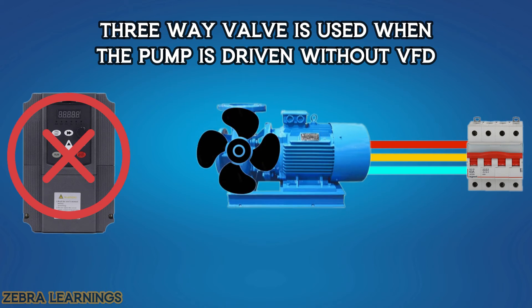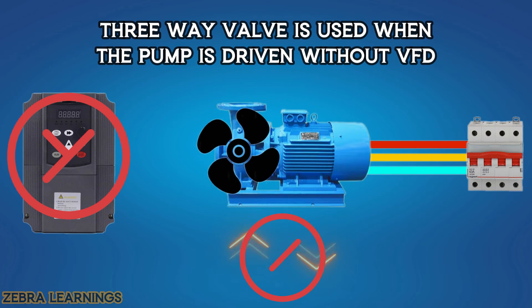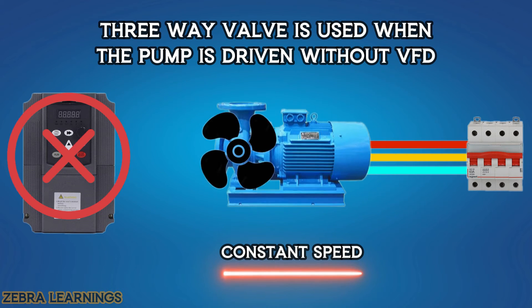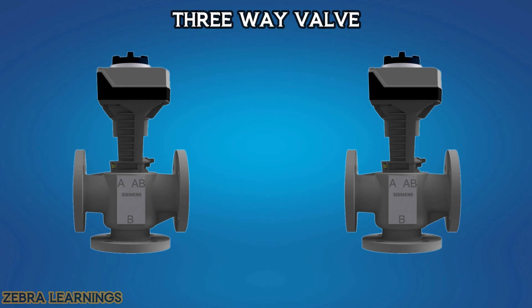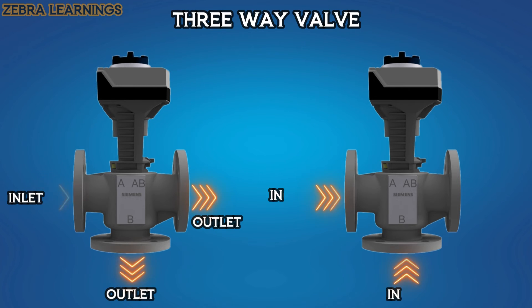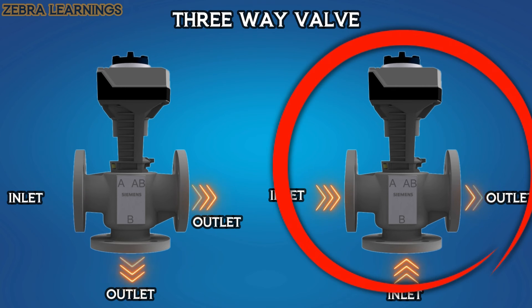If the pumps are driven directly by electricity, the speed of the pump cannot be increased or decreased — it runs at constant speed only. There are 2 types of 3-way valve: one is a valve with 1 inlet and 2 outlets, and the other is a valve with 2 inlets and 1 outlet. But in AHU, the valve with 2 inlets and 1 outlet is used.